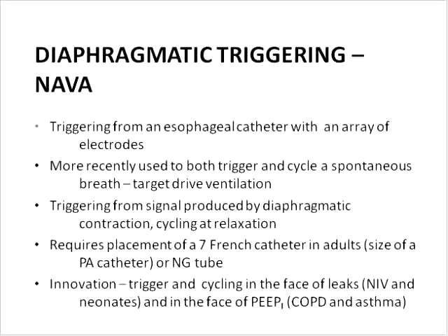The signal is produced by the diaphragmatic contraction and cycling at relaxation, usually 80% of the peak diaphragmatic signal. It does require that you put a 7 French catheter in adults or an NG tube that replaces your current NG tube. And it's very innovative. I mean, in terms of being able to trigger and cycle in the face of leaks during non-invasive ventilation and in neonates, and I'm always telling people, in an adult who breathes 16 times a minute, changing the trigger delay by 5 or 10 or 15 milliseconds probably is of very little consequence. And a kid who's breathing 90 times a minute, it might make all the difference in the world.